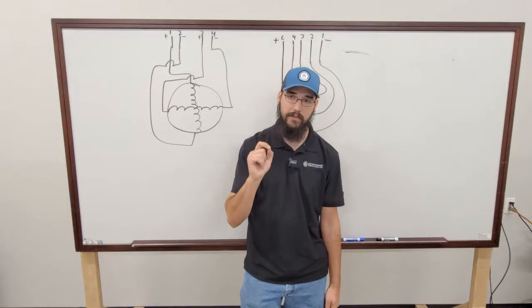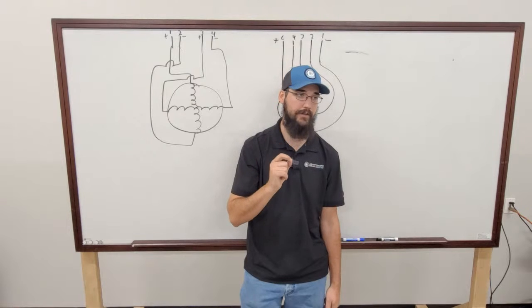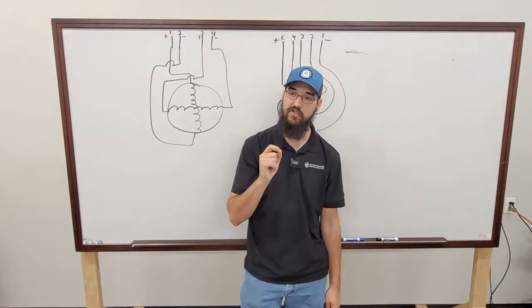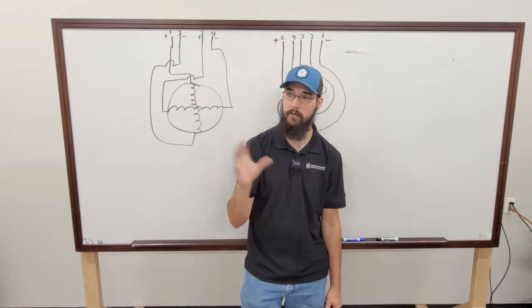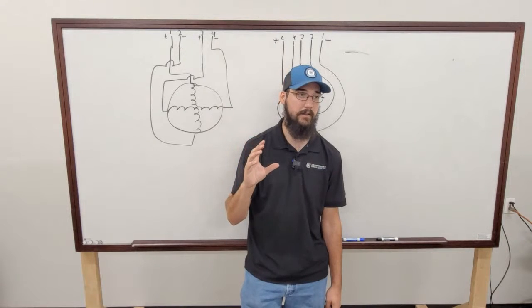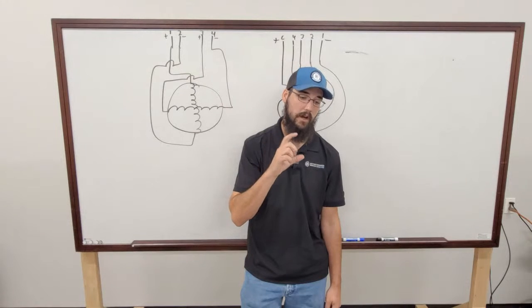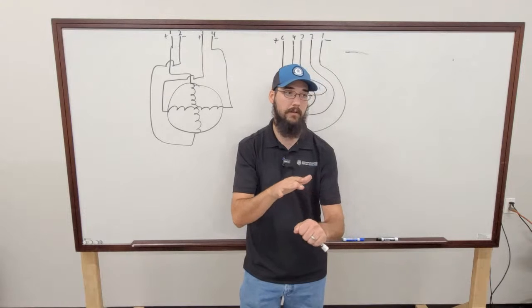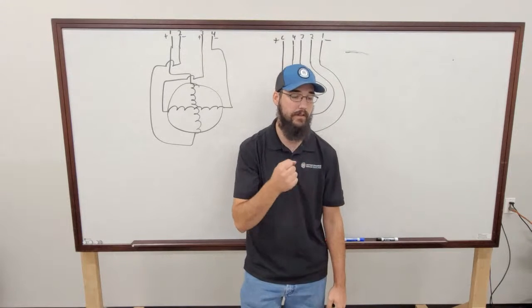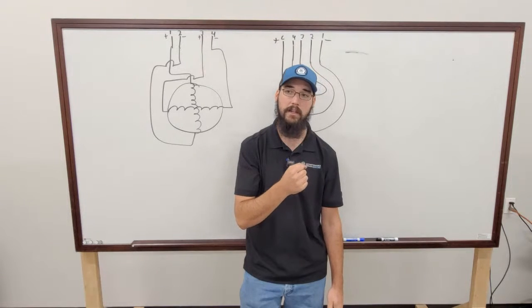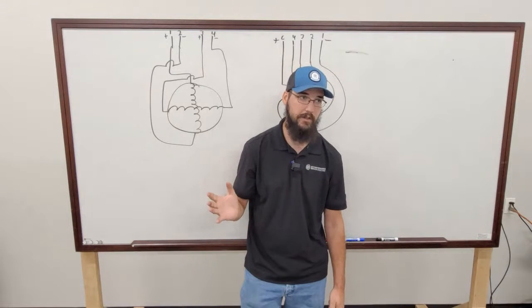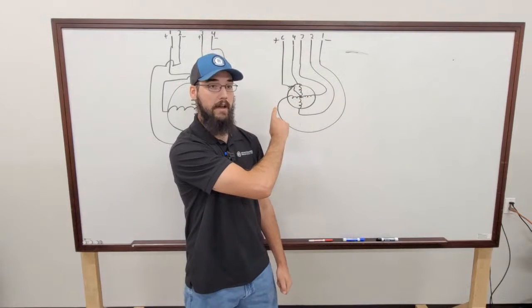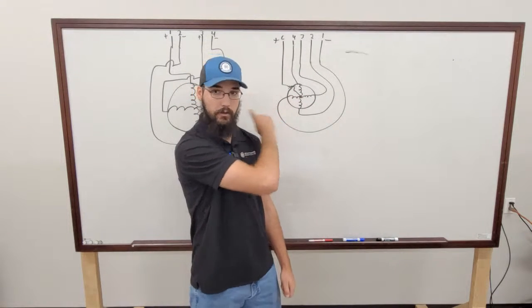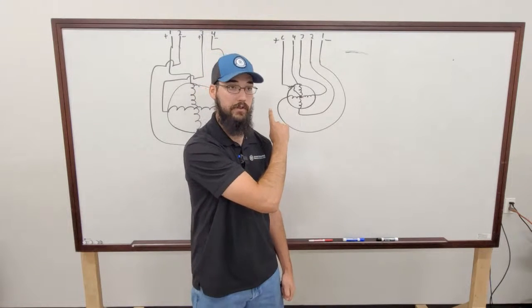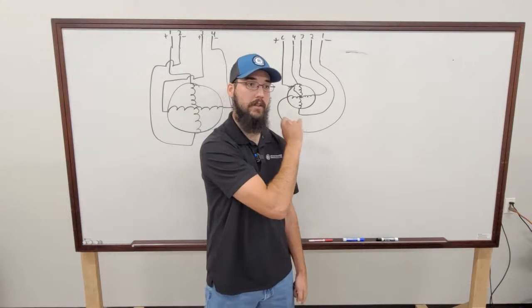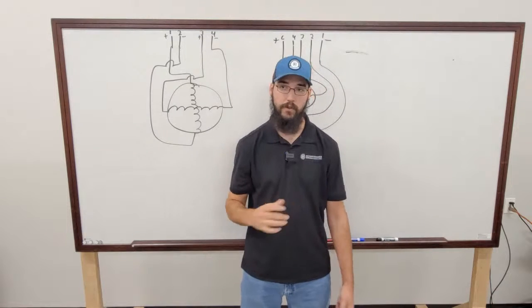Now, I can tell you, EXVs, for the most part, should be fairly quiet in their operation. If you walk up and that EXV is just excessively ticking, like you can easily hear it from anywhere, you need to start asking questions about that valve. Because it's requiring a lot of extra load on that motor of the EXV in order to move it, and it shouldn't have to do that. If you're having to do that, it's very likely that you're missing steps, which is throwing your calibration off. Because remember, neither of these have a reference indicator. There is no reference indicator going back to the control system to tell it I'm in X position. It is all done in the logic. Floating point. That's all it is.